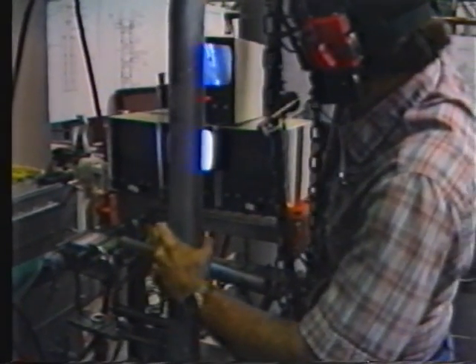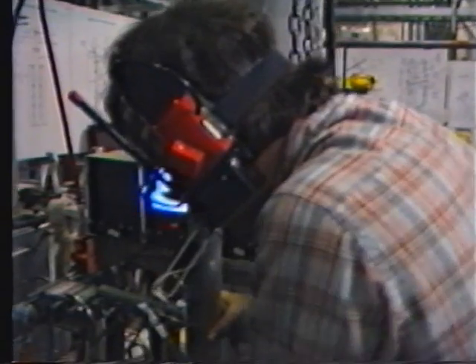A rotating work platform developed by Westinghouse in cooperation with the Department of Energy was installed on top of the open reactor vessel. By rotating this platform, all parts of the upper core debris bed can be reached. A 6-inch thick stainless steel floor shields the defueling operators from radiation. At Three Mile Island Unit 2, defueling crews trained for months on a full-scale mock-up outside of the reactor building before starting this defueling work in October of 1985.